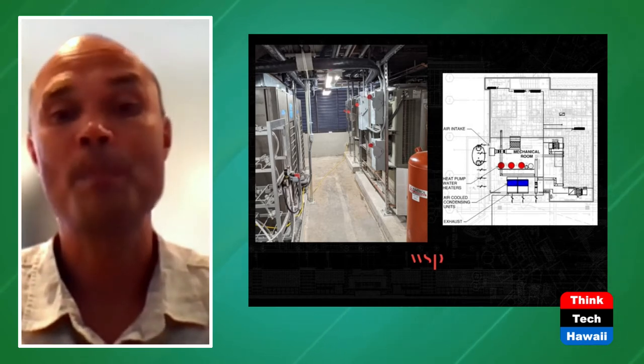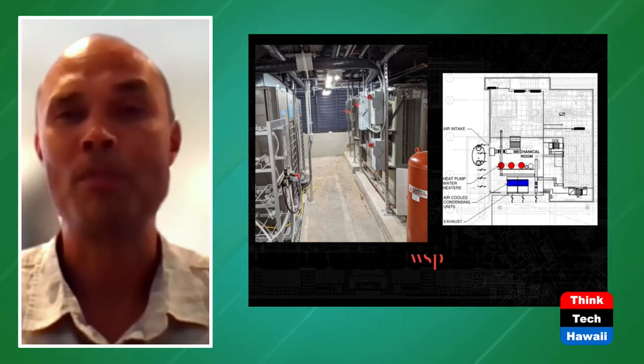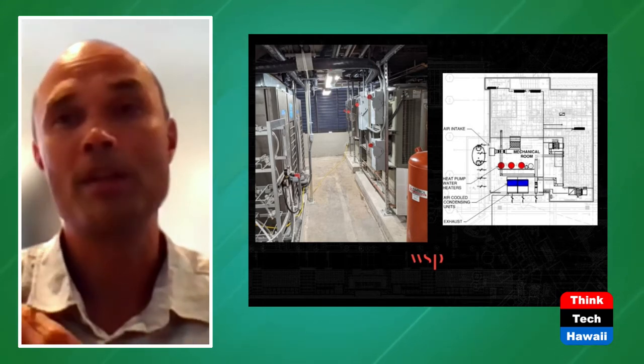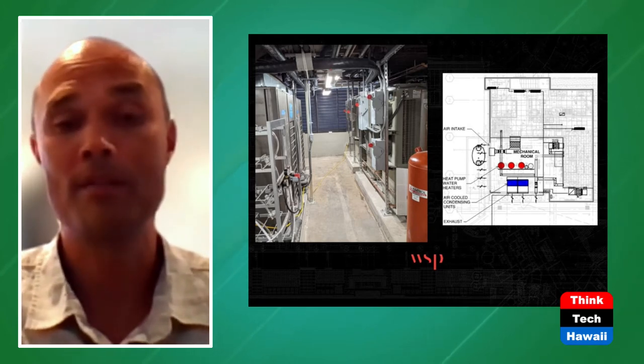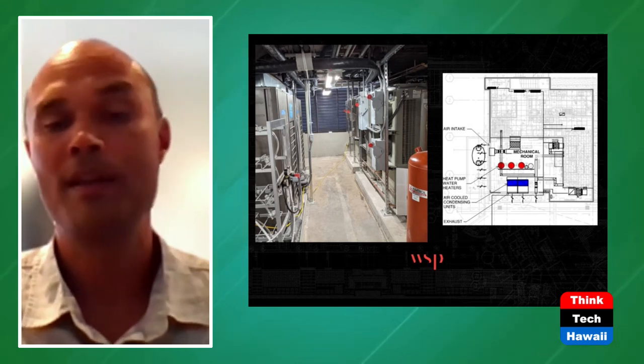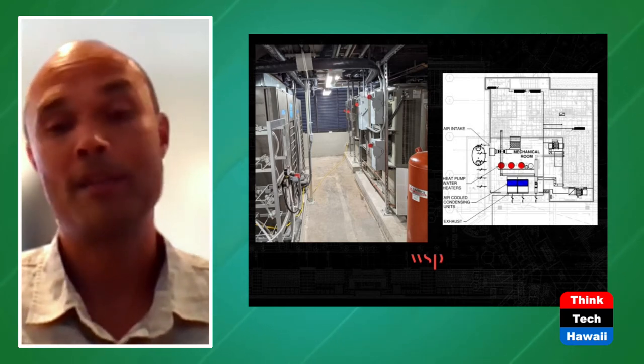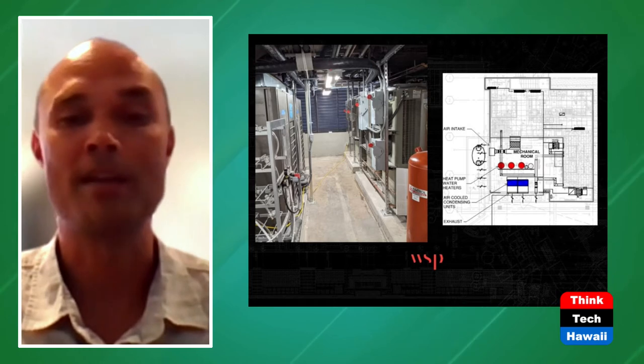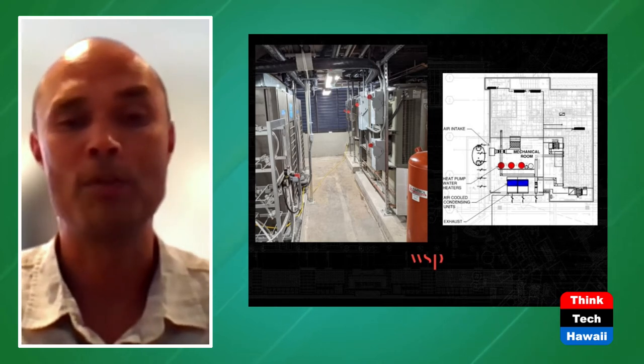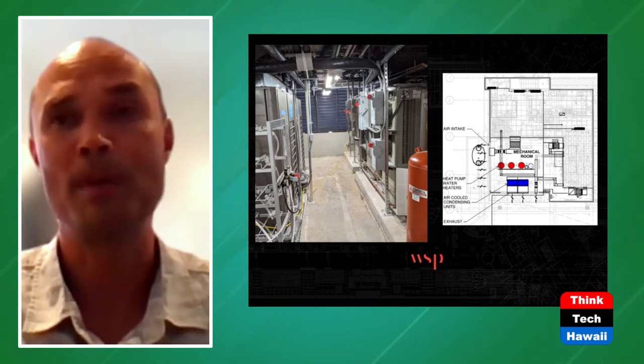And we figured, okay, if we provide heat pumps to heat the hot water and then provide air cooled condensing units through a VRF system for the air conditioned property, we can locate both of them inside the basement. And they'll work somewhat congruently because heat pumps want the space to be hot and they'll reject cool, because it'll be taking the coolness of the water to create hot water. And then the air cooled condensing units want a cool space, and then they'll take that cool air and pull it out of the space and blow it outside.